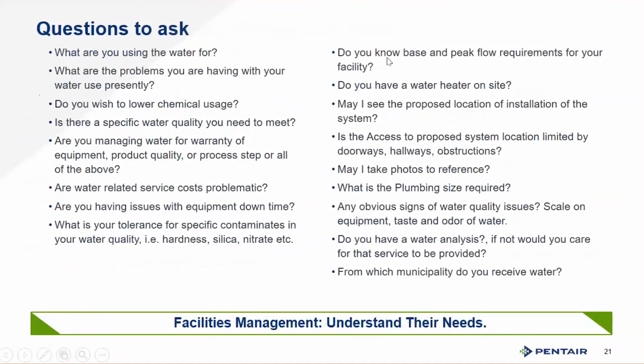Do you know base and peak flow requirements of your facility? What problems are you having with your water use presently? Do you have a water heater on site? Can you see the proposed location of the installation? Is access to the proposed system location limited by doorways, hallways, and obstructions? May I take photos for reference when you get on site? What plumbing size is required? Any obvious signs of water quality issues? Scale on the equipment, taste and odor?